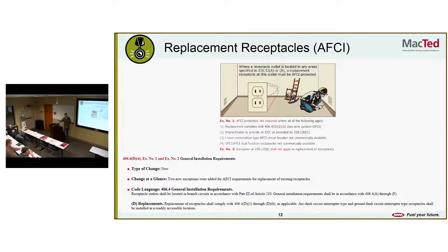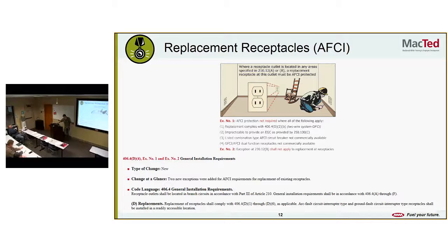Replacement receptacles. Oh, arc fault. Looks like we have a new change here for general installation requirements. 2 new exceptions were added for AFCI requirements for replacement of existing receptacles. Receptacle outlets shall be located in branch circuits in accordance with Part 3 of Article 210. General installation requirements shall be in accordance with 406.4. Replacement receptacles shall comply with 406.4 through D6. Arc fault circuit interrupter type and ground fault circuit interrupter type receptacles shall be installed in a readily accessible location. So what they've added is an exception. It shall not apply to replacement receptacles. So if it's located in an area specified in 210, a replacement receptacle at this outlet must be AFCI protected.